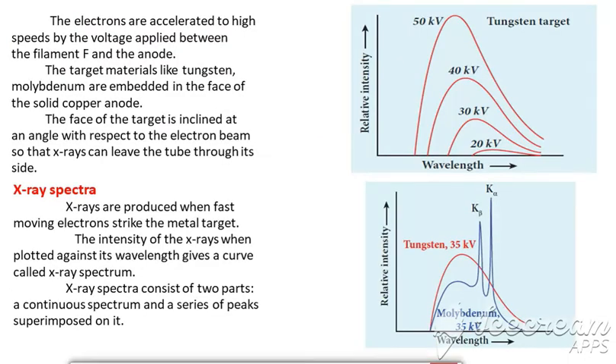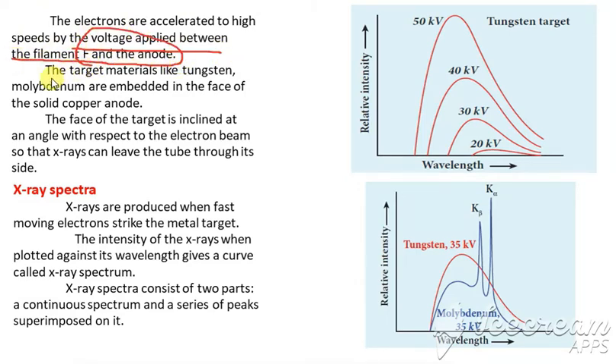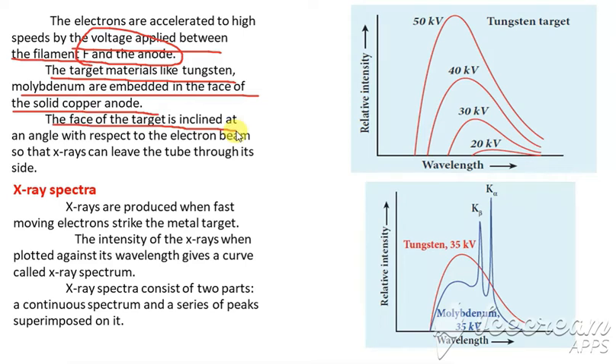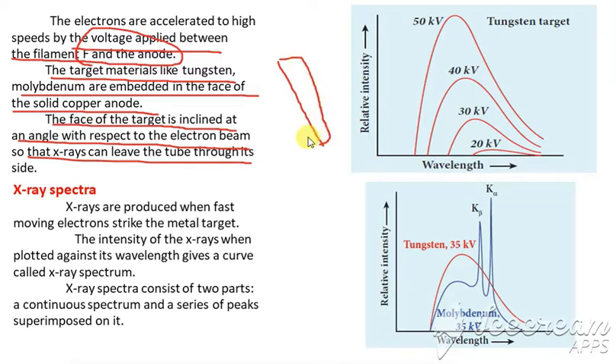The electrons are accelerated to high speeds by the voltage applied between the filament and the anode. The target material — such as tungsten or molybdenum — is embedded in the face of a copper anode. The face of the target is inclined at an angle with respect to the electron beam.